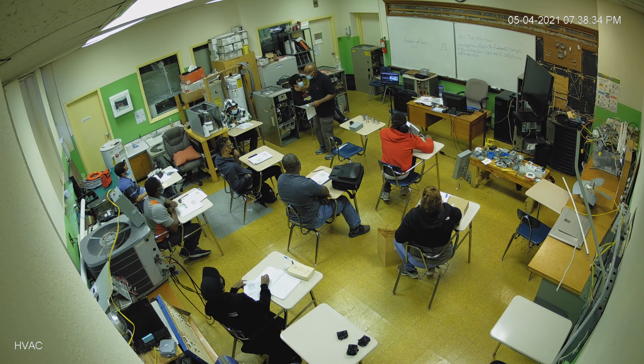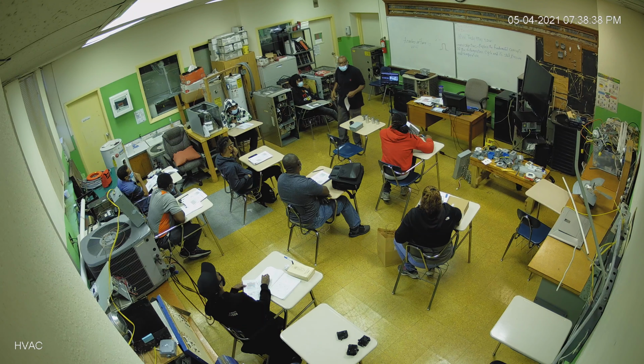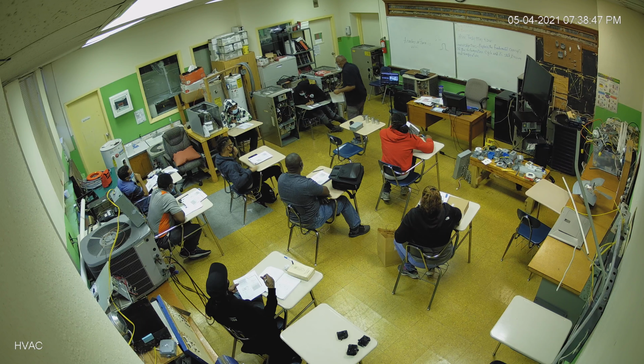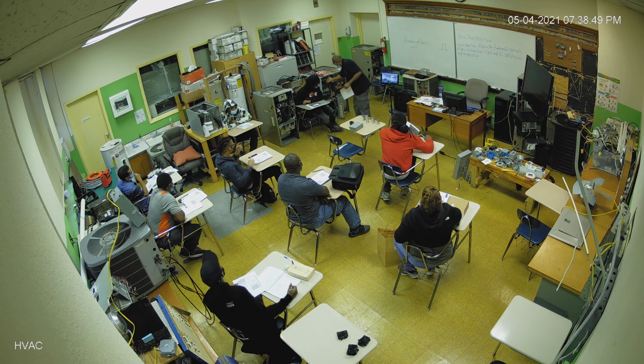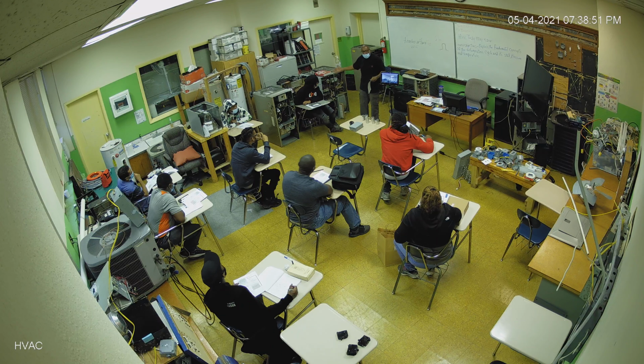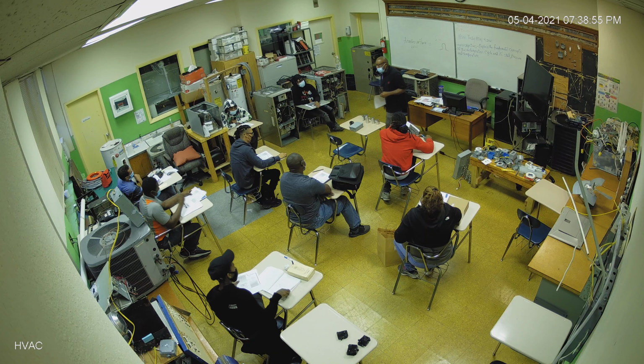The motor? No, that's the last thing to come on. What motor, the blower motor? No, that's the blower motor, that's your fan, that's your blower motor at the bottom. The first thing that comes on is this here, your inducer motor. That's the first thing that comes on.